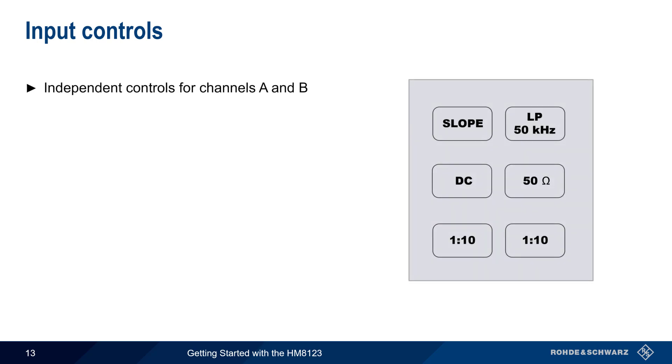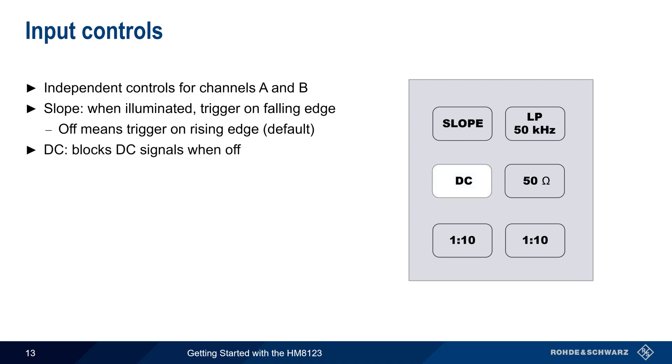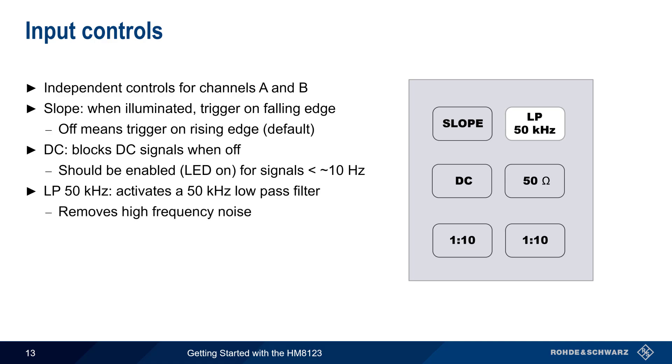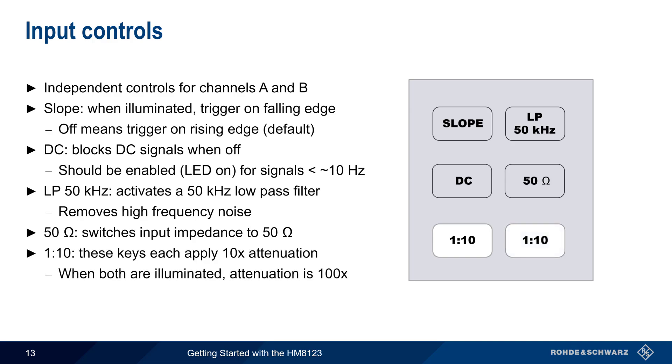Independent input controls are provided for both channel A and channel B. When illuminated, the slope key indicates that triggering is being done on the falling edge of the input signal. When the LED is off, then triggering is being done on the rising edge, which is also the default. The DC key blocks DC signals when off, but it should be enabled when measuring signals with a frequency of less than approximately 10 hertz. The LP 50 kilohertz key activates a 50 kilohertz low-pass filter, which can be used to remove high frequency noise on the input signal. The 50 ohm key changes the input impedance from 1 megaohm to 50 ohms. And finally, the two 1/10 keys each attenuate the input signal by a factor of 10. If they are both enabled, the total attenuation factor is 100. Keep in mind that proper signal attenuation is important for accurate measurement results.